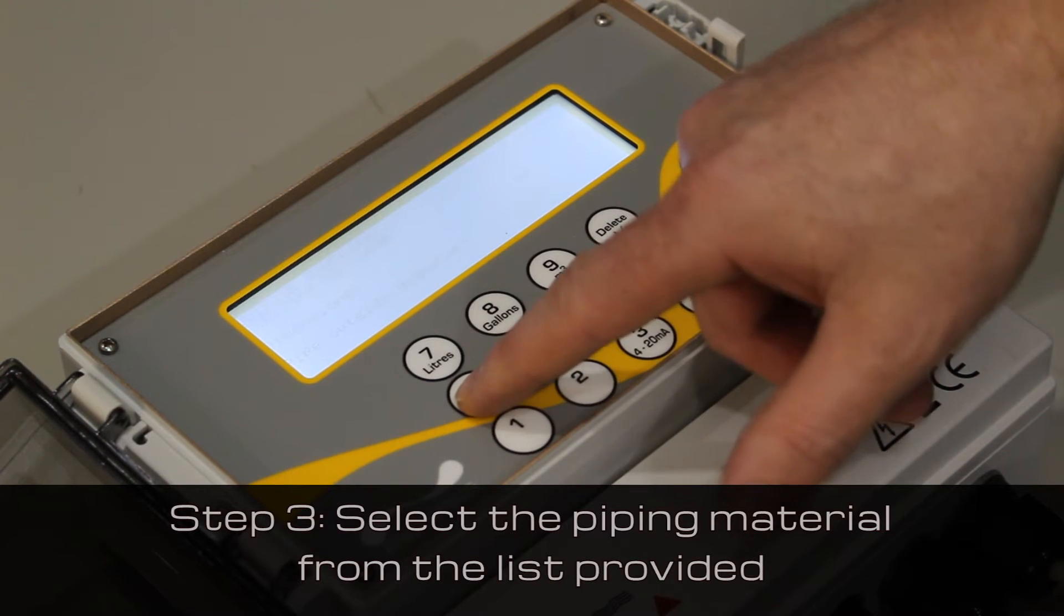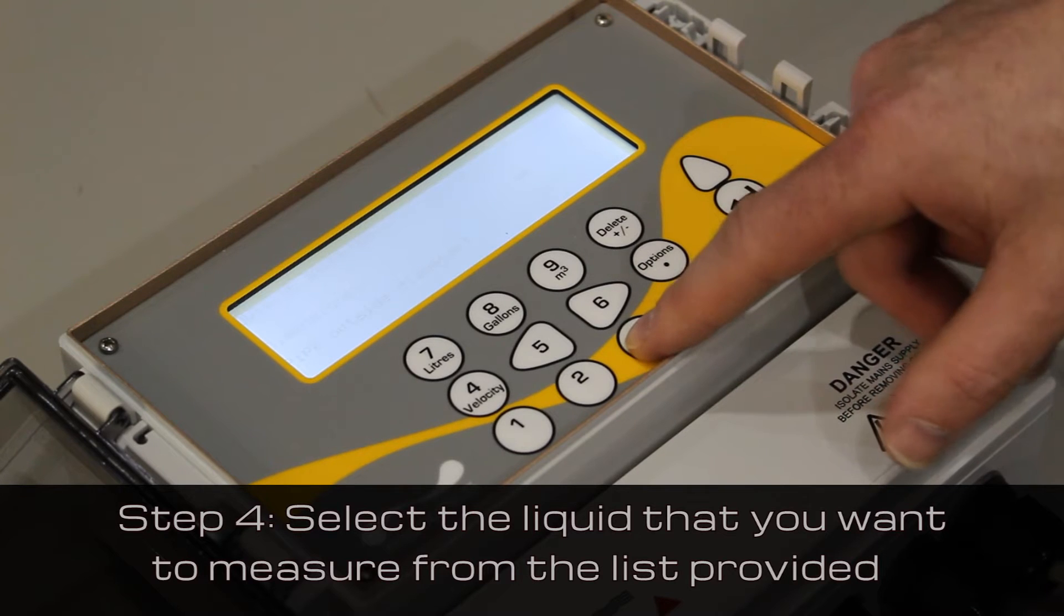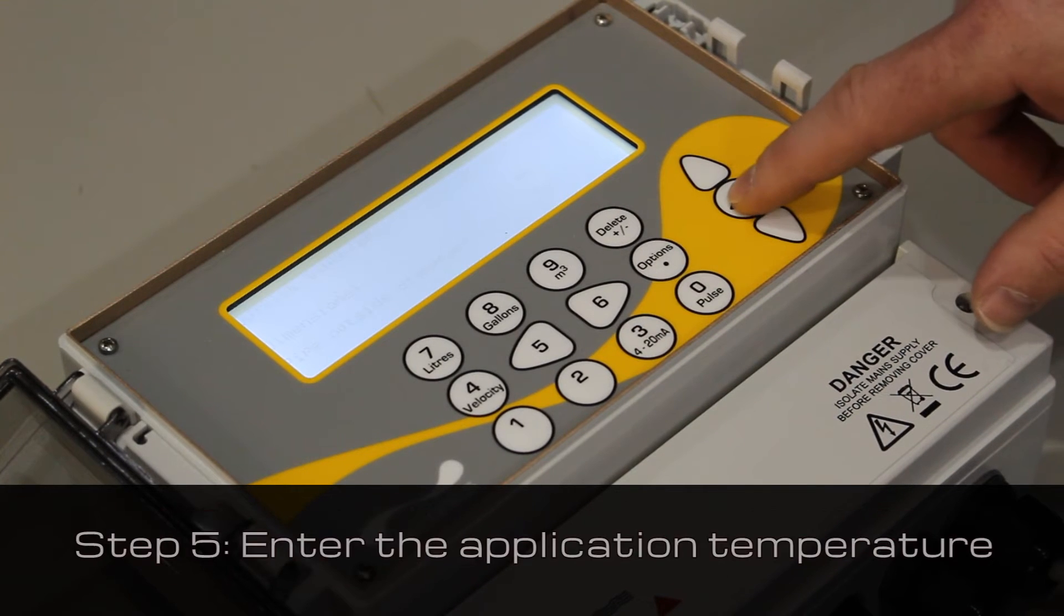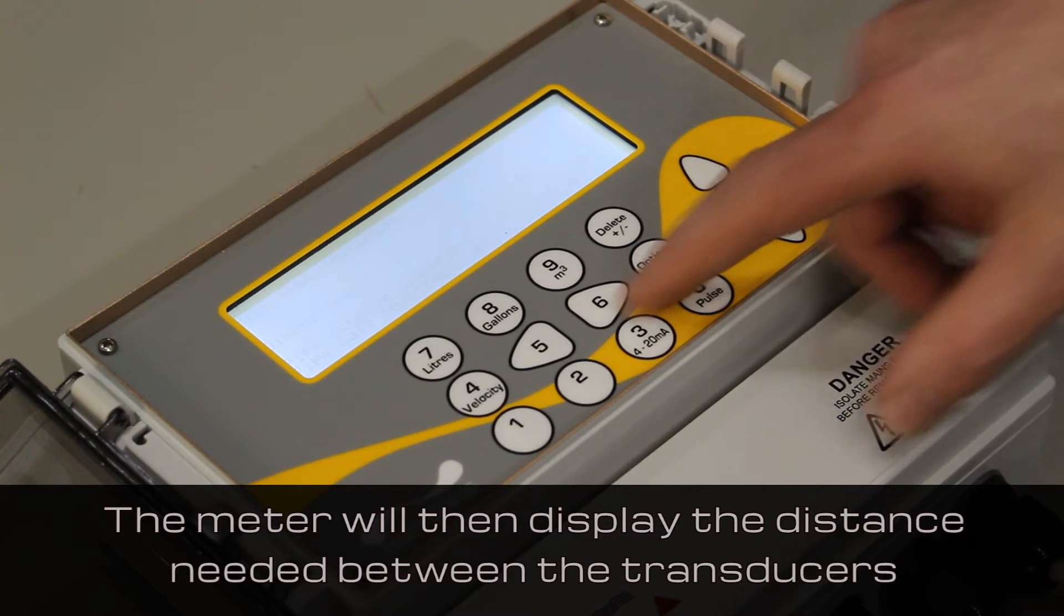Then select the piping material from the list provided. Next, select the liquid that you want to measure from the list provided. Enter the application temperature. The meter will then calculate the distance needed between the transducers and will display it on the screen.